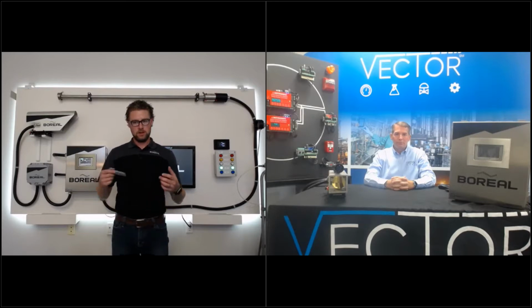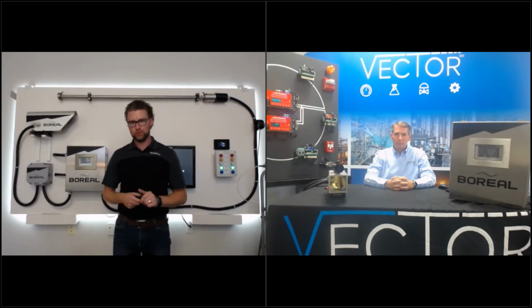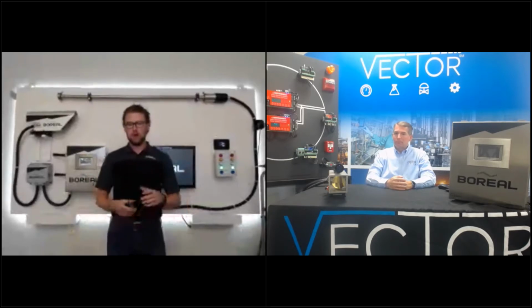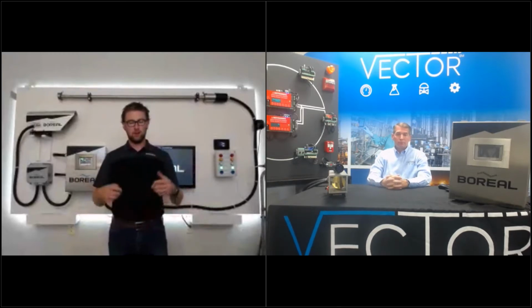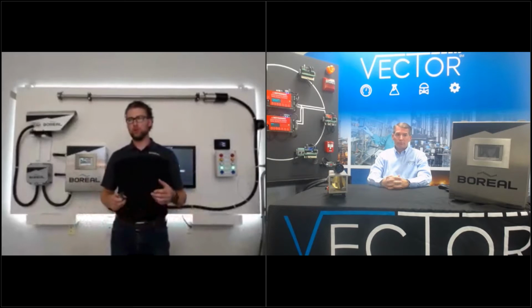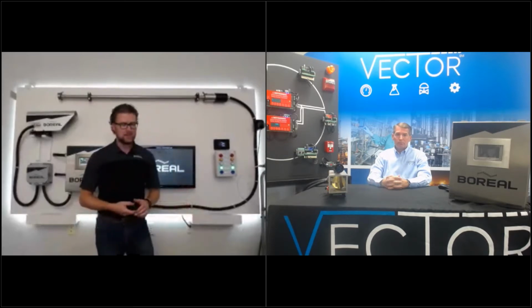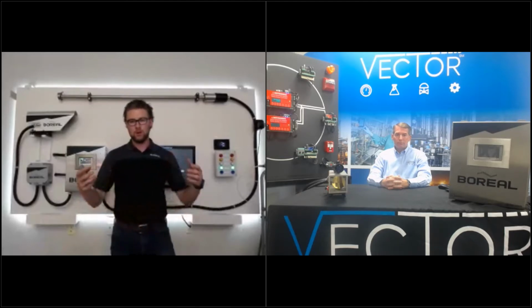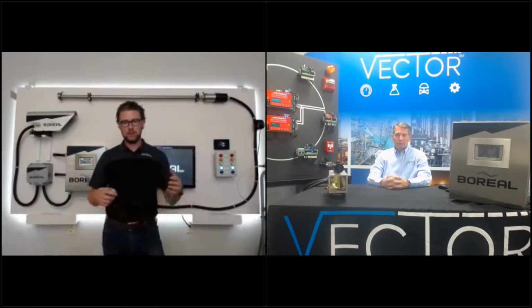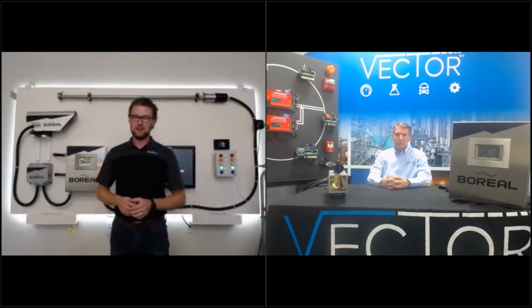So before we start, I really want to emphasize why this particular equipment, this enhanced sensing element, is so important for your facility's fire and gas safety system. On the screen, to Chad's right, what you're looking at are the parts and components that can fully formulate a complete fire and gas safety system. Why you as an end user would have a whole fire and gas safety system is purely for the purpose of risk mitigation. Think of it as sort of an insurance policy that, with physical hardware along with your fire and gas safety system, will enable the recovery after a loss of containment as soon as possible.